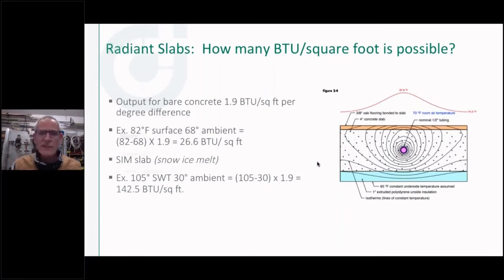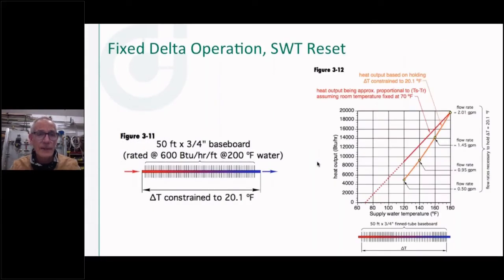On the previous one, this was a fin tube that we modeled this with. Again, Siggy did the model, and there's 50 feet of 3/4 baseboard. And there's the output of the baseboard, and that's where the math didn't come out exactly right, but that's where we tried to constrain, and that's what this graph is showing, a piece of 3/4 fin tube. Is it copper or cast iron? Copper fin tube. Okay, yeah, that's copper.